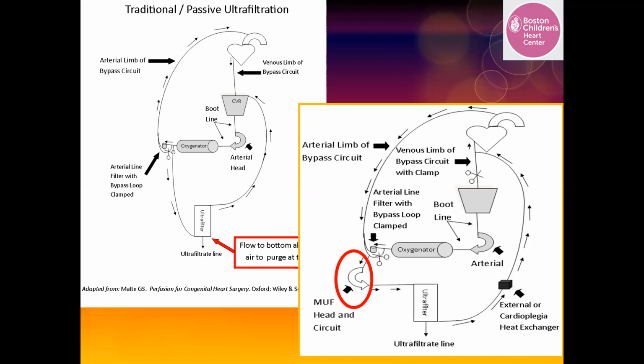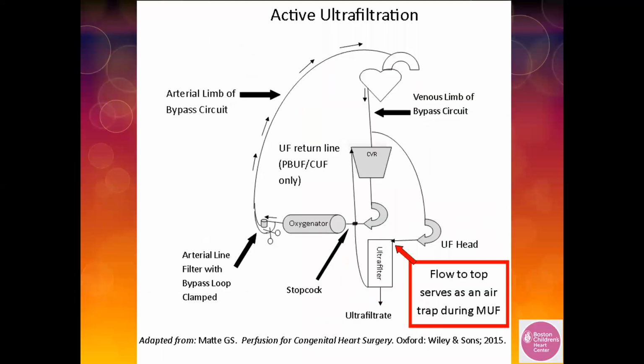It is my belief that perfusionists should standardize to active ultrafiltration for the entire case for a few simple reasons. And this active ultrafiltration must source blood from the venous limb of the circuit. That is exceptionally important to prevent the possibility of entraining air into the blood across the hollow fiber membrane oxygenator. So let's take a look at the setup that I believe is exceptionally safe and effective.